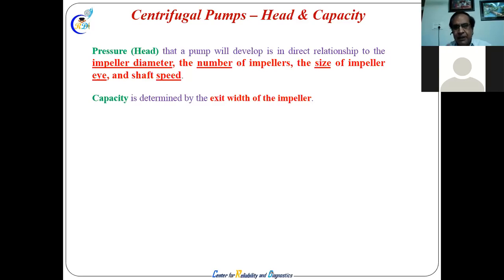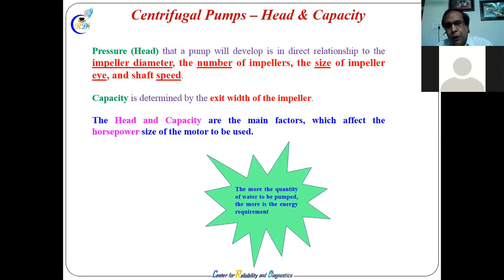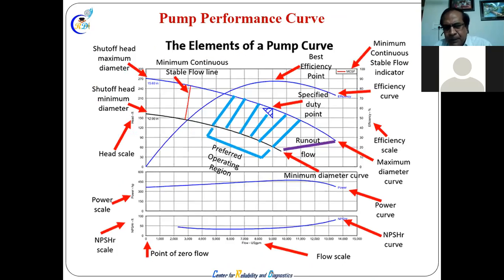Capacity is determined by the exit width of the impeller. So the more water you pump, the more energy is also required. This is an element of a pump curve. This is the best efficiency point, and these are the maximum diameter and the minimum diameter. Okay, this much diameter with this efficiency. Suppose this is the maximum efficiency point. The efficiency point is this line, so this is the preferred operating range.